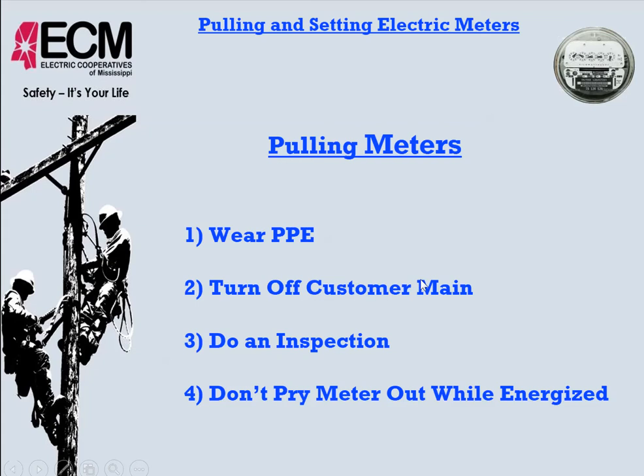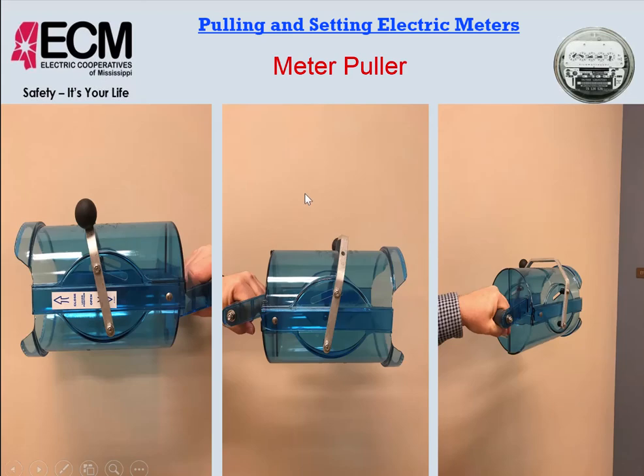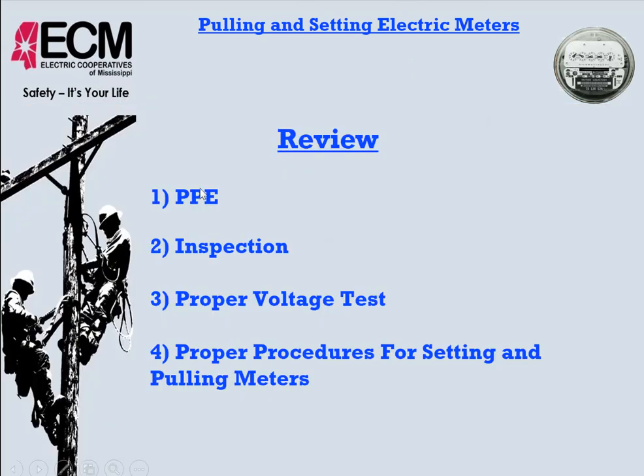This is not a load break or make device. Do an inspection. Do not pry the meter out while energized. You can try to pull a meter out with your rubber gloves, face shield, hard hat, arc-rated clothes on, but if it's taking an unusual amount of force to get it out, probably want to go de-energize it before you proceed. Also make this little device as a meter puller. If there was a problem or arc flash, it would be contained inside and directed away from you. But also it helps use some leverage there to help pull the meter out, some of those that are just a little sticky. Okay, so review: PPE, inspection, proper voltage test, proper procedures for pulling and setting meters.